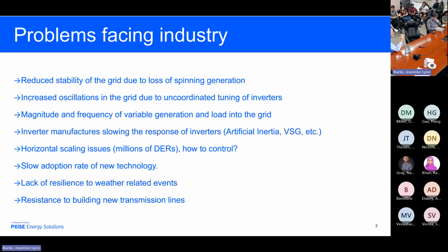So the industry is pushing very hard to provide artificial inertia, and it's causing trouble for our company. I have several examples where I could not achieve the objective that we promised to the utility, because the inverter manufacturer will not allow us direct control. We have to send an indirect control.